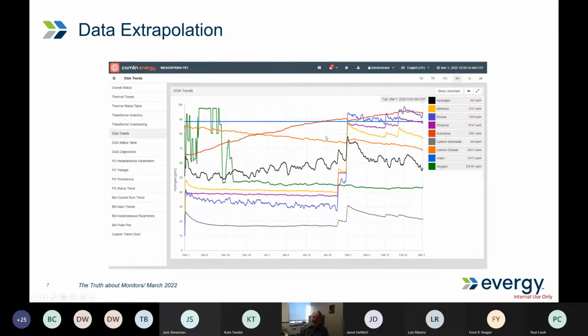The catch about this particular piece of equipment is we put a monitor on it because it's about 71 years old. Some people wouldn't allow a transformer to stay in service that long. I have some transformers that are 99 years old, and I hope we keep them one more year so we can have a century-old transformer in service, carrying load. We're doing oil testing on those to make sure they're still functioning as designed, and they are. They have a different trend -- you have to look through a different set of goggles to make sure they're healthy.